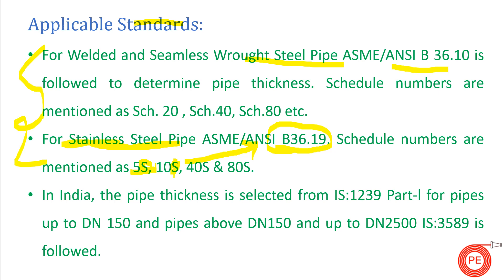Both ASME standards refer to American standards. In India, pipe thickness is selected from IS 1239 Part 1 for pipe sizes up to DN 150. For pipe sizes greater than DN 150 up to DN 2500, IS 3589 is followed. In Indian standards there is no concept of schedule numbers; instead, different thickness criteria are mentioned in IS 1239 Part 1 and IS 3589 for different pipe sizes.